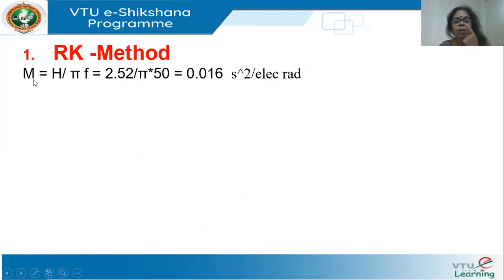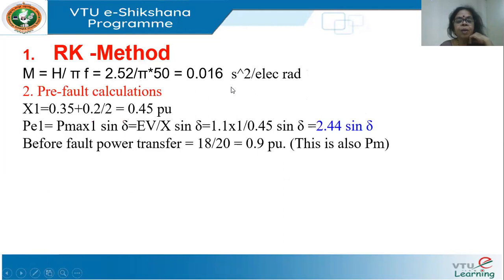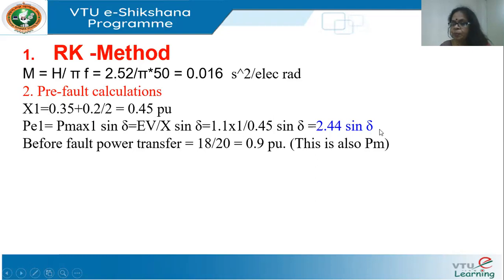M is H by π·f, which gives 0.016 seconds per electrical radian. Pre-fault, I have two lines of 0.2 per unit reactance in parallel, and the generator reactance is 0.35. So x1 is 0.45 and Pe1 = 2.44 sin δ. P_max before the fault is 2.44. The power transfer is 18 MW, i.e., 0.9 per unit, which is also equal to the mechanical power.